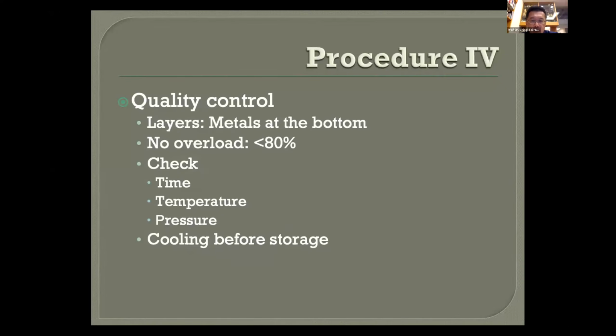So after packing, we put the packs in the sterilization equipment, and we have to have some quality control measures. Of course, when we put the items into the containers, they have to be layered. Usually we put the metals at the bottom and the light things on the top. Especially for the metals, sometimes after the high temperature evaporation, there are vapors, and they may drip down onto the surface of the layers at the bottom. So it's better to put the metals at the bottom layer and other items on the top. And of course, no overload for the container, not to load more than 80% of the space.